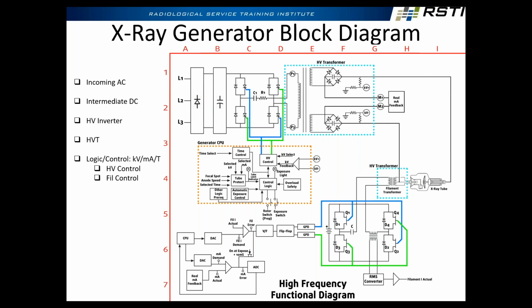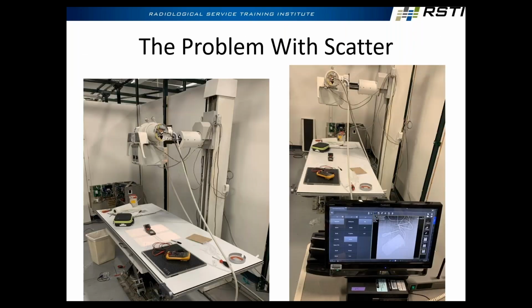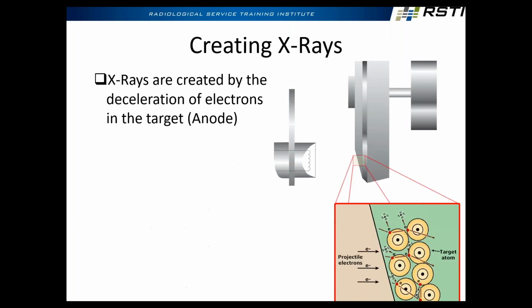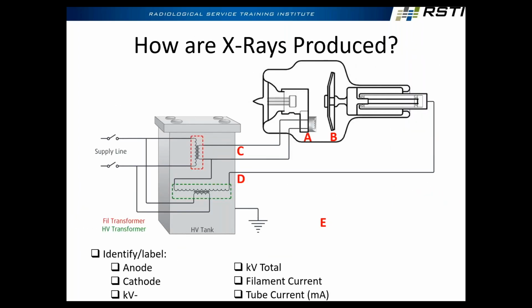So we have logic and control, which is controlling the high voltage, which would be the orange in this case. Like pick your time, pick your mA, the control for actually making the high voltage. And then we also have filament control as well. Why do you think the filament current might change, for example? Why would you have to change the filament current? Yep. Let me go back to my X-ray tube slide here. We all agree that filament current is running through here, right? We all agree that tube current is running through here. We all agree that kV is the difference between those two points. If filament current was, let's make up something, 3 amps, and you change the kV from 80 kV to 100 kV, what's going to happen to your tube current?